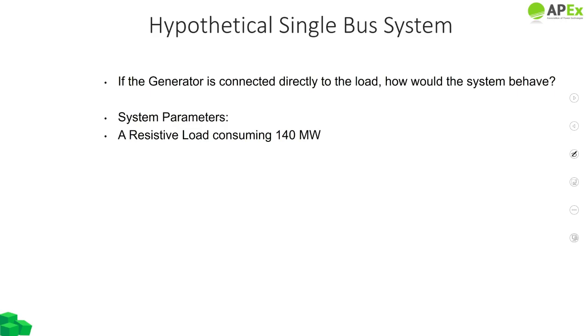To understand this, we have made an example in which a generator is directly connected to the load and the load is resistive. We will see how the system behaves. The given is that a generator which can generate up to 240 megawatts is connected to a resistive load of 140 megawatts. So essentially this means that this load draws no reactive power, and the system therefore would not produce any reactive power in this case. We have done this analysis on a global simulation software, a snippet of which would be shown now.